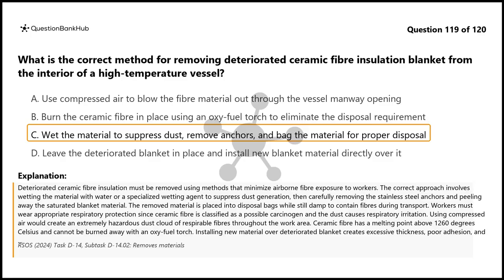Ceramic fiber has a melting point above 1260 degrees Celsius and cannot be burned away with an oxy-fuel torch. Installing new material over deteriorated blanket creates excessive thickness, poor adhesion, and trapped moisture that degrades the new insulation.